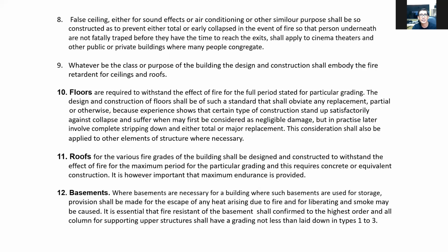Floors are required to withstand the effect of fire for a full period stated for a particular grading. The design and construction of floors shall be of such standard that shall obviate any replacement, partial or otherwise, because experience shows that certain types of construction stand up satisfactorily against collapse and may at first be considered as suffering negligible damage, but in practice later involve complete stripping down and either total or major replacement. The consideration shall also be applied to other elements of the structure where necessary. So in case you have floors that are highly combustible, these floors should be replaced immediately after the fire, or other components of the building that have caught fire should be replaced.